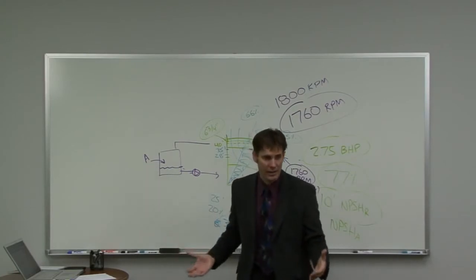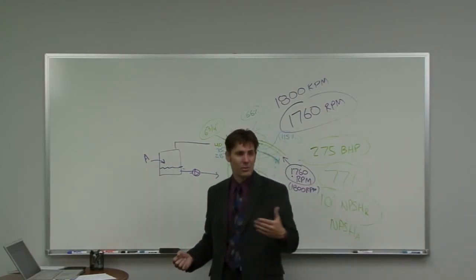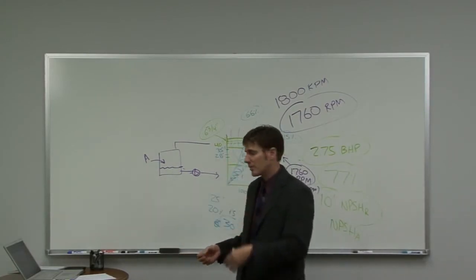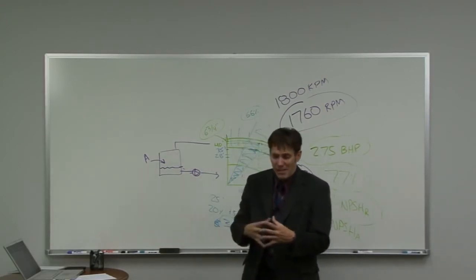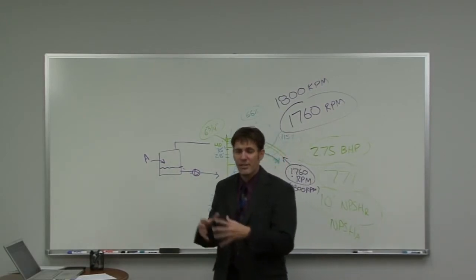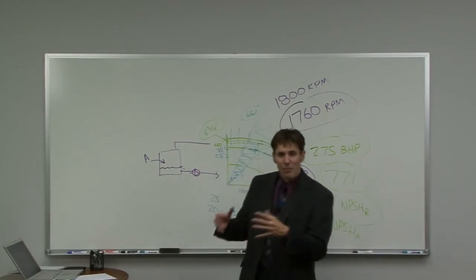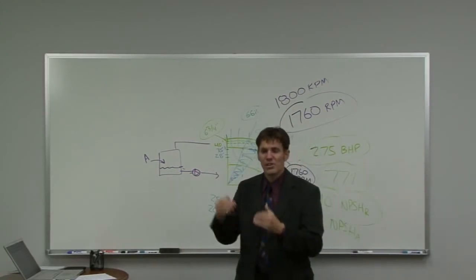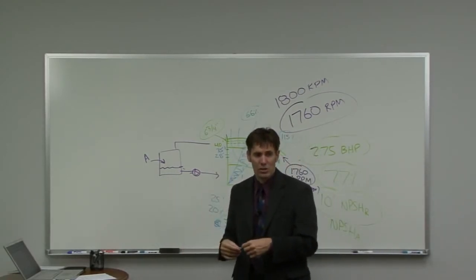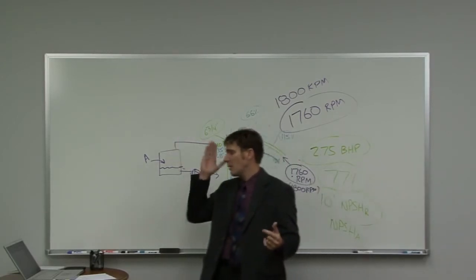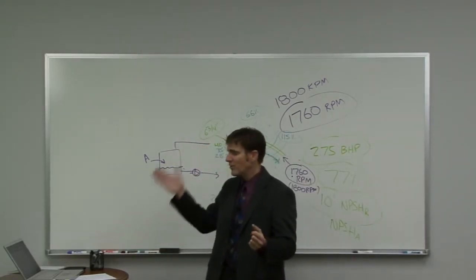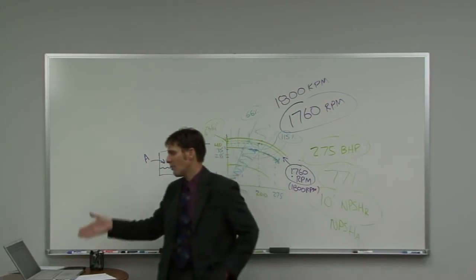It's based on the affinity laws. We do teach other classes on our website about the affinity laws, and it will help you understand that. But I'm expecting my flow rate to go up 150 gallons per minute. My pressure is going to go up a squared function of that change. It's going to be huge. There's no way this pump could even do that. There's no way that the system could take that, so there's no way you'll ever operate there.